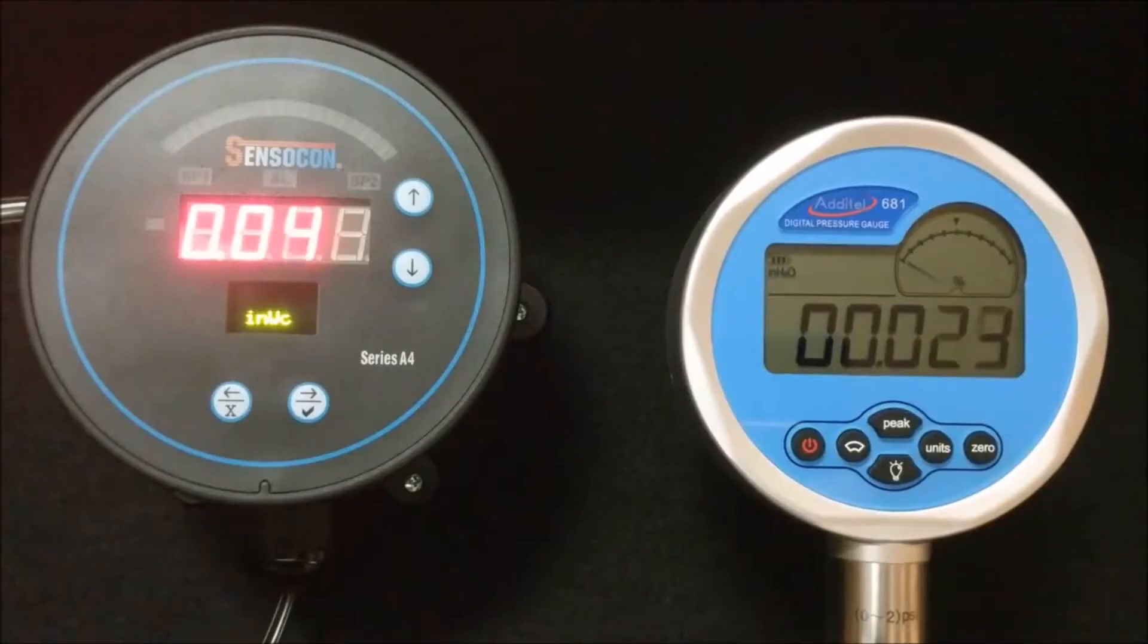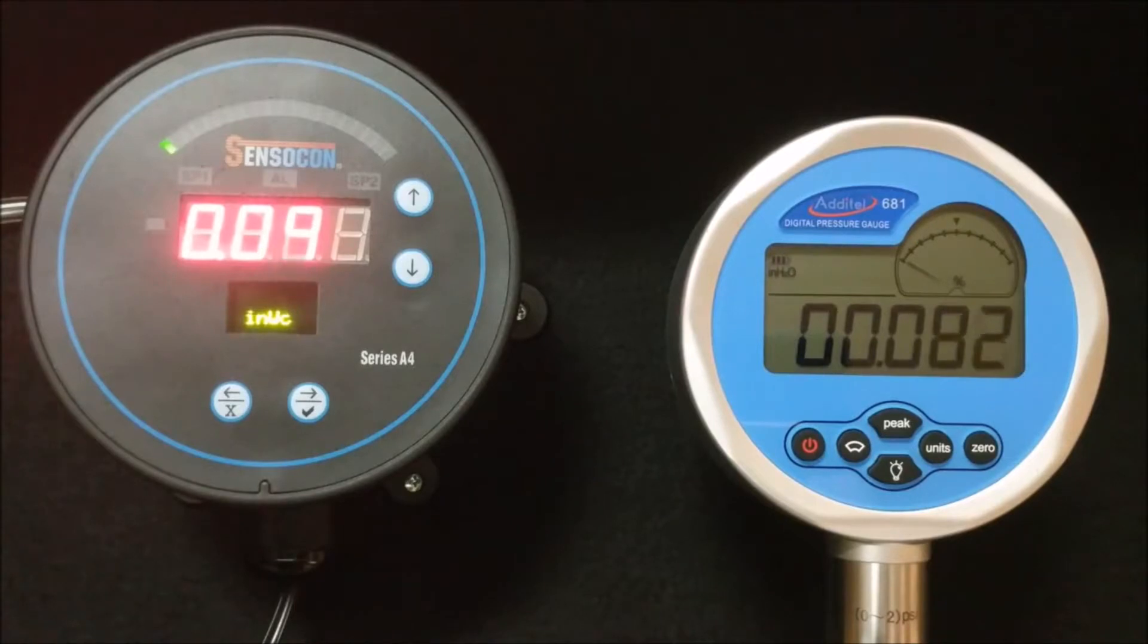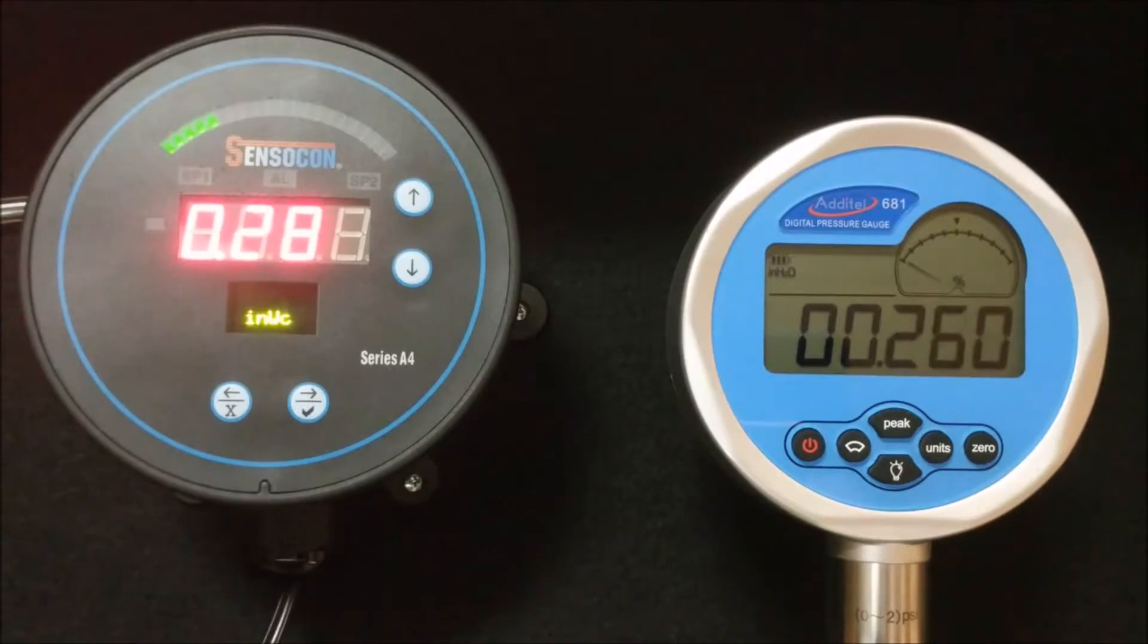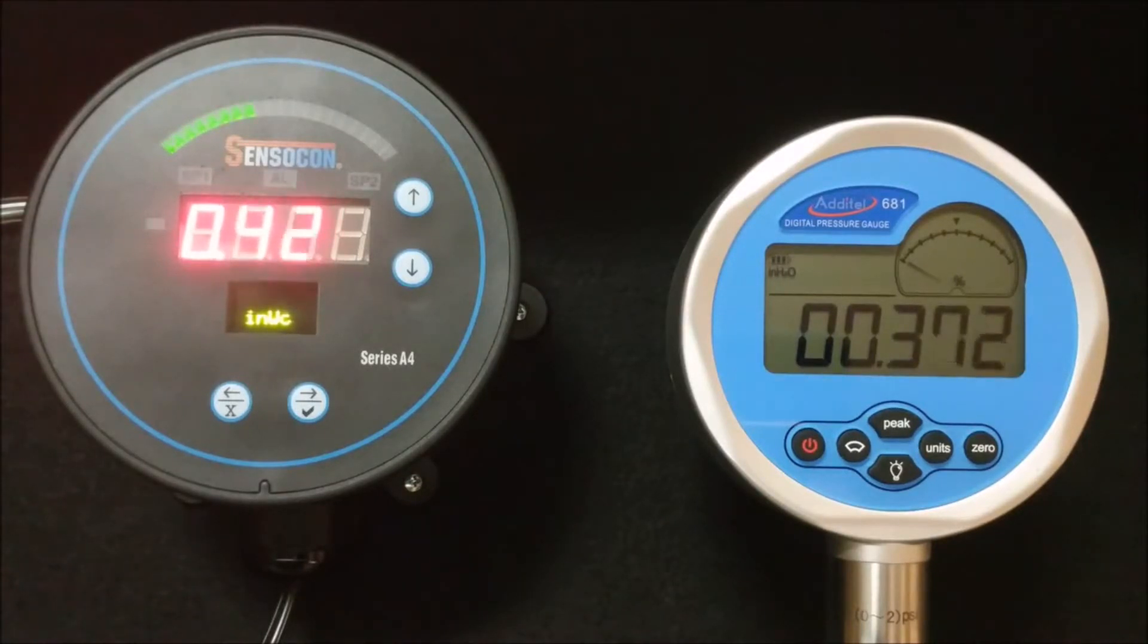Span is another calibration feature you can use, but should only use it if you have the ability to accurately source the full scale pressure. This function is also located in the secure menu right below the zero feature.